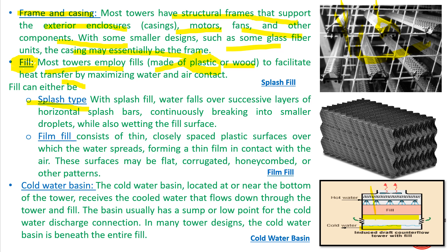There are two types of fills: one is your splash type and another is your film fill. In the splash fill, the pieces are independently separated from each other. In the film fill — which may be corrugated or honeycomb-shaped — water gently flows from the top downwards, and these sections are stacked one above the other.